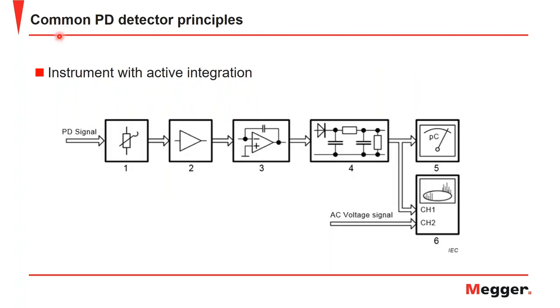Next, we have an instrument with the active integration, where your partial discharge signal is fed into, again, the attenuator, then fed to an amplifier, an integrator, and then the peak detector and evaluation unit here, and then ultimately, again, the meter and oscilloscope. And with this design, the evaluation unit has the task to ensure that the behavior is according to the weighting curve of the IEC 60270 standard.